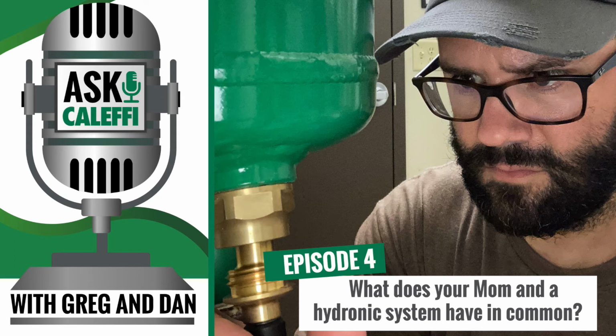Well, they work pretty similar to that air separator. They reduce the velocity. They slow down the fluid passing through the coalescing mesh, which allows that mesh to knock the dirt and debris loose. That dirt and debris will fall down into the bottom of the separator. The magnetic portion, when you have the magnetic separation, that'll pull out very fine magnetite.